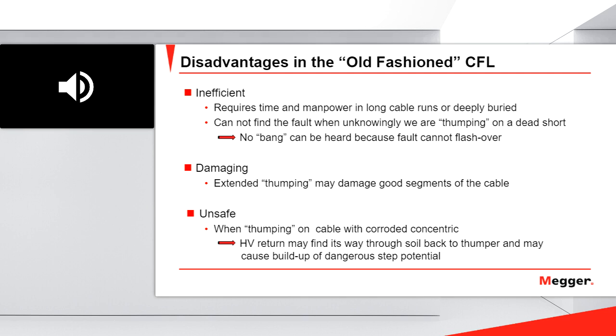Also, normally when we use this process, we spend a lot of time trying to pinpoint the fault. And if we thump the cable for many, many hours, at the end we will damage our cable. And also, it's unsafe. It's unsafe because let's say that we are trying to find a fault, and in some segments of my cable the concentric is corroded. So if the ground is wet and I am walking along the route of the cable, there will be a problem, because maybe I will be the one that closes the circuit where the concentric is corroded, and I will suffer a step potential, okay? So these are some of the disadvantages of this method, and for that reason we no longer recommend this method of fault location.